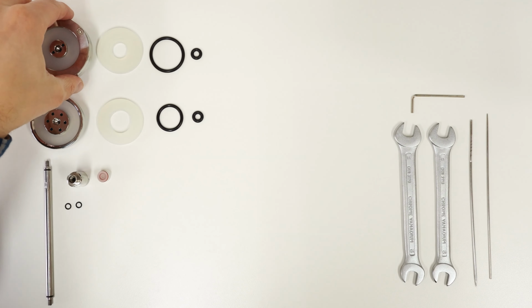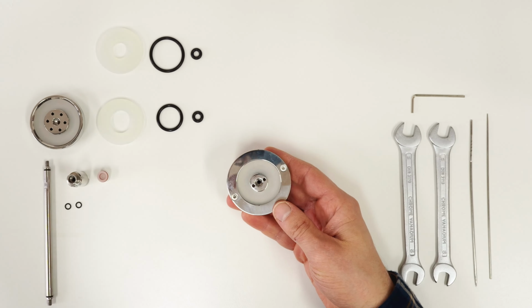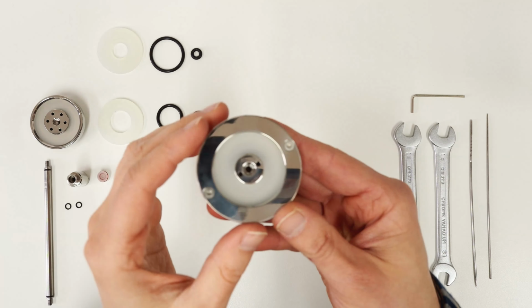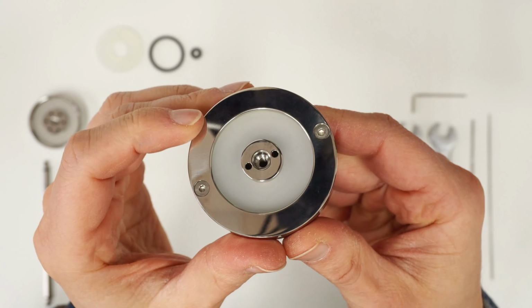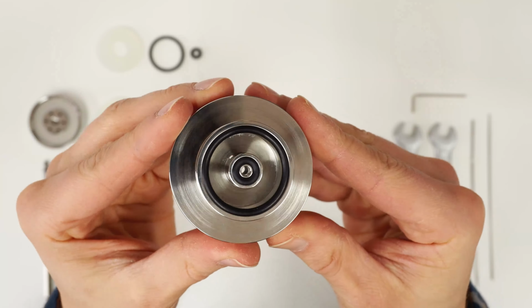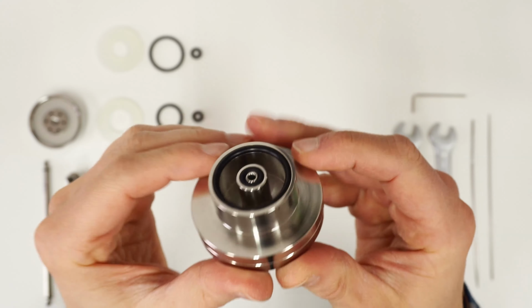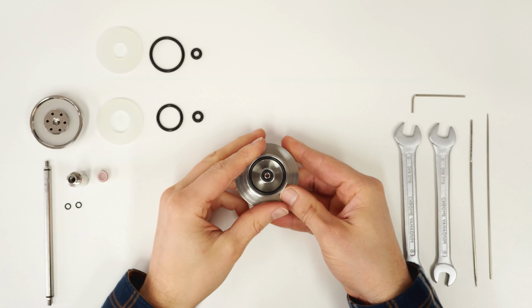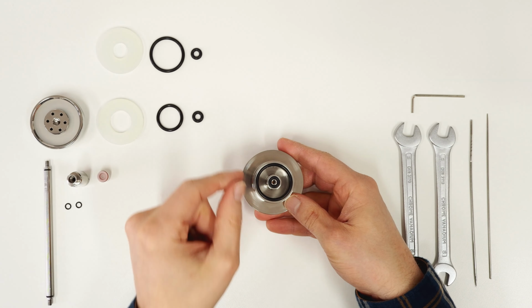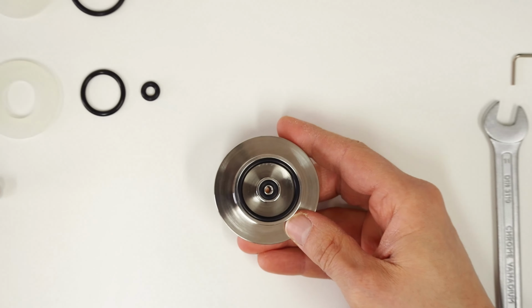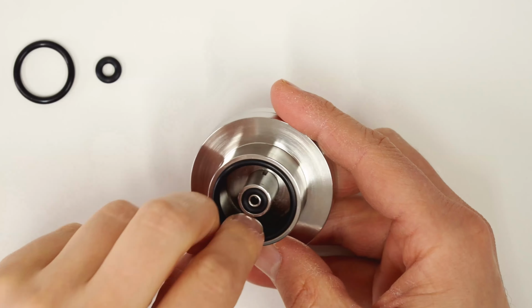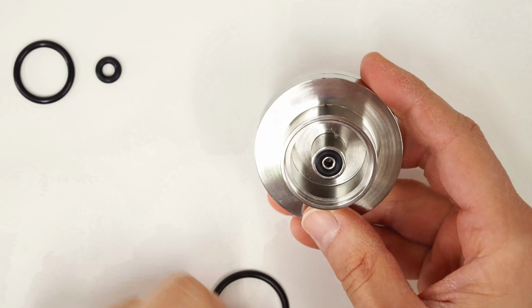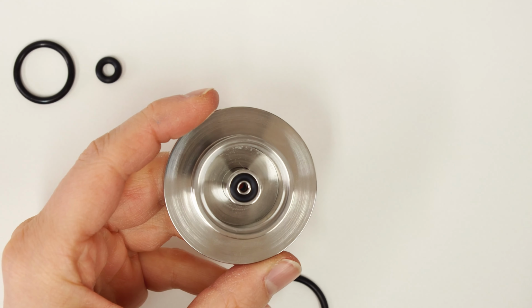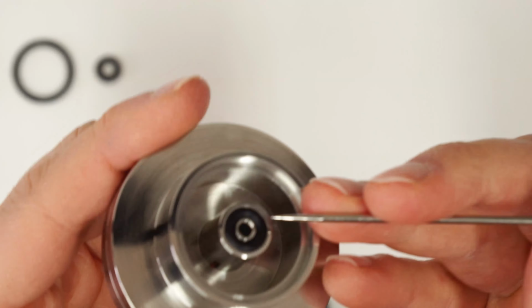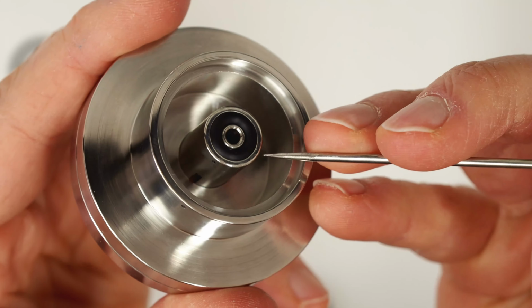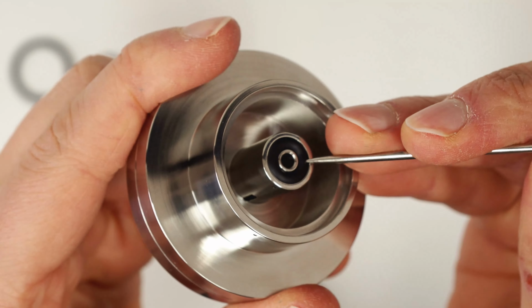Let's start with the probe head. Here we have a total of 3 seals, 2 O-rings at the top and a large silicone seal at the bottom. Let's begin with the O-rings. The larger one can be removed very easily. The smaller one is a bit more difficult. For this, you can use a needle for assistance. If you puncture the O-ring, it cannot be reused.